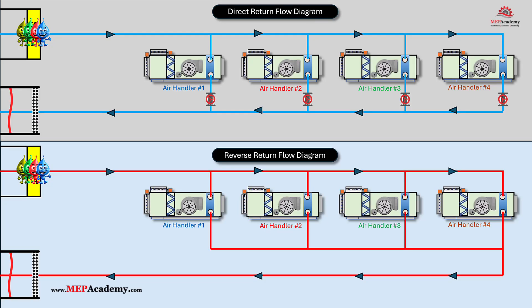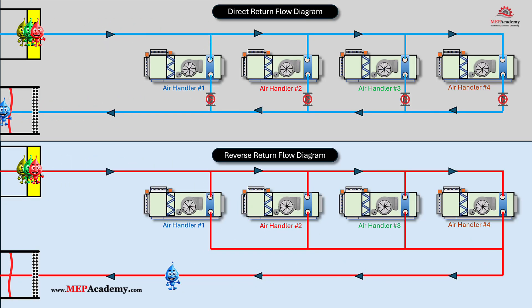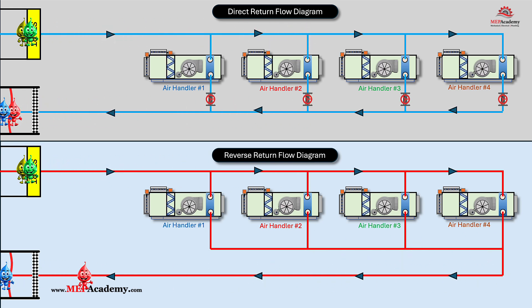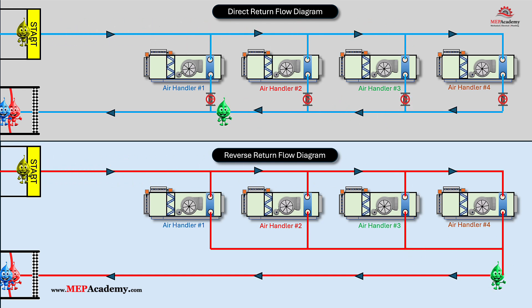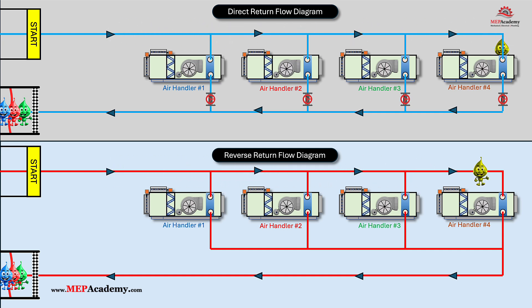In HVAC water-based systems, water distribution is critical to ensure that each terminal unit receives the correct amount of heated or cooled water. Two popular piping configurations — direct return and reverse return — are often used in these systems. Each configuration has its unique benefits, potential drawbacks, and implications for water balancing and system performance.